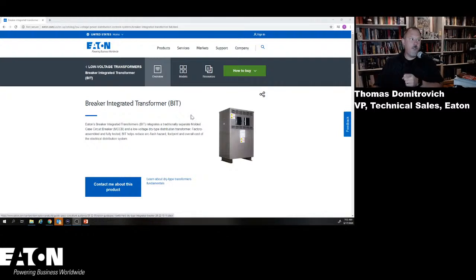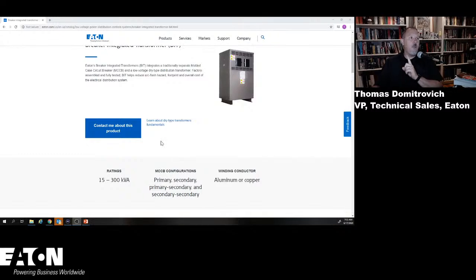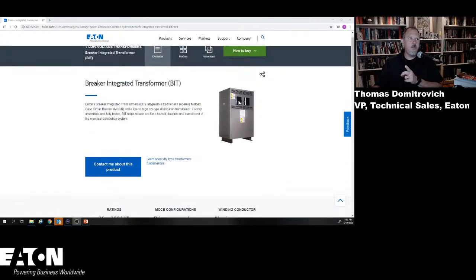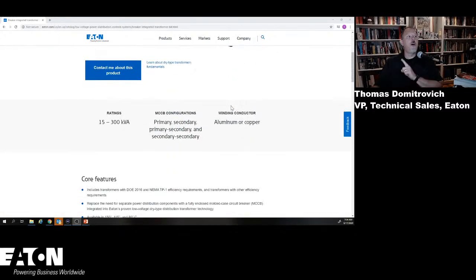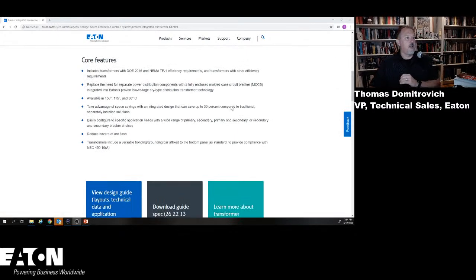What we did with this solution is we integrated, as you'll see right here, the primary and secondary. You can get this thing with just a primary breaker or just a secondary breaker or both. I'm going to give you some examples of why I think both of those give you some value. I personally am tied to the secondary breaker being tied into the transformer, and I'll show you why from a safety perspective here in a second.